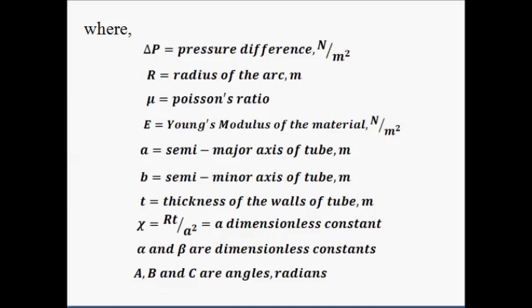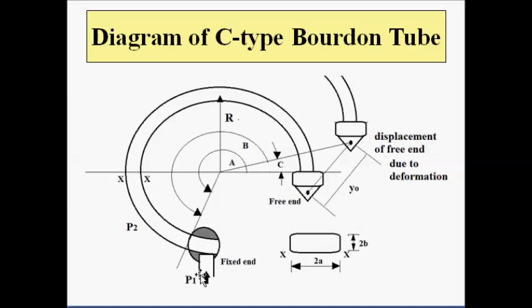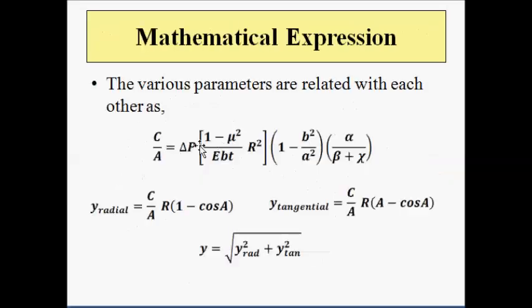To summarize the working: the fixed end of the C-type Bourdon tube is kept on a rigid base connected to the source of pressure to be measured. Whenever there is a change in pressure — when outside pressure differs from inside pressure — the tube undergoes deformation, causing displacement of the free end. This displacement Y-subscript-O can be related to the differential pressure and the coiling angles A, B, and their difference C using the mathematical expressions, allowing calculation of radial, tangential, and net displacement.